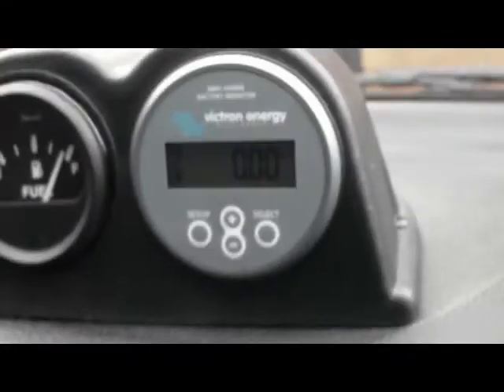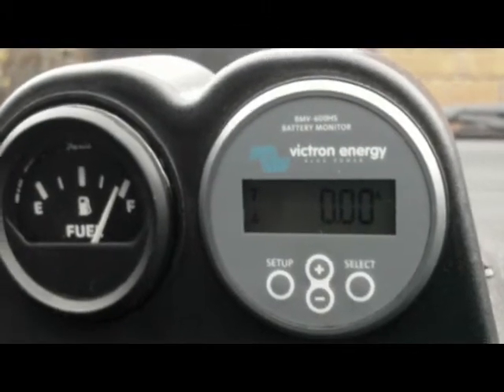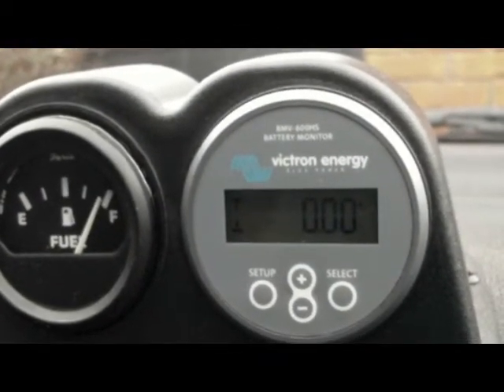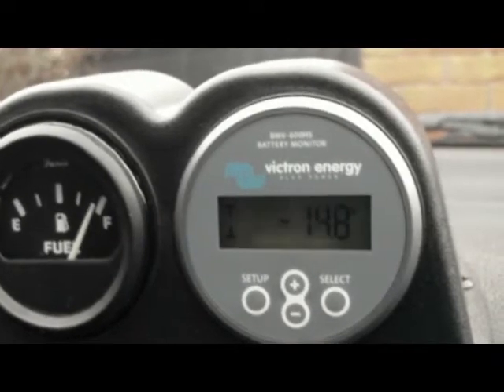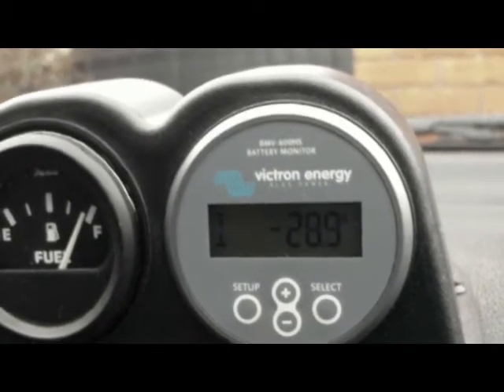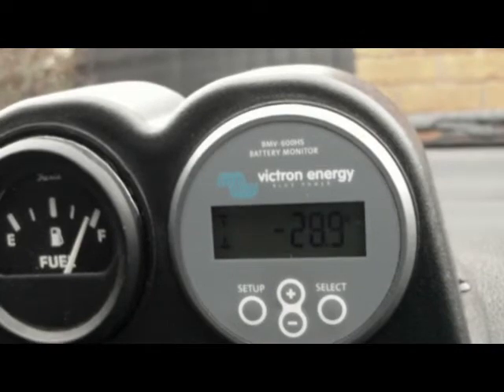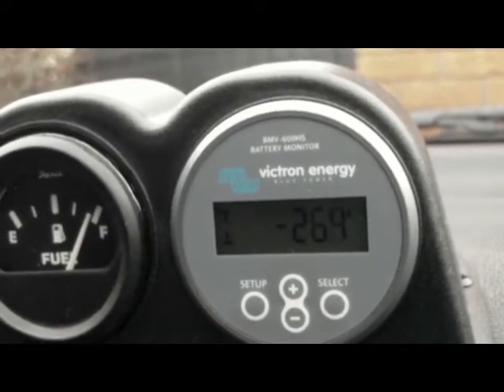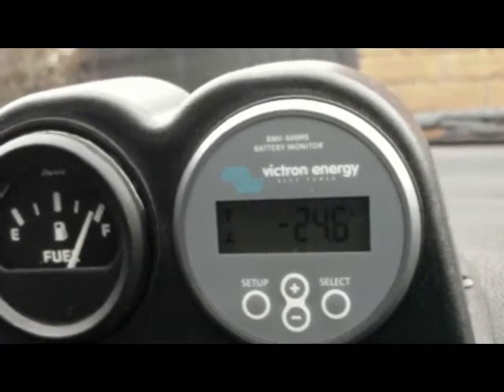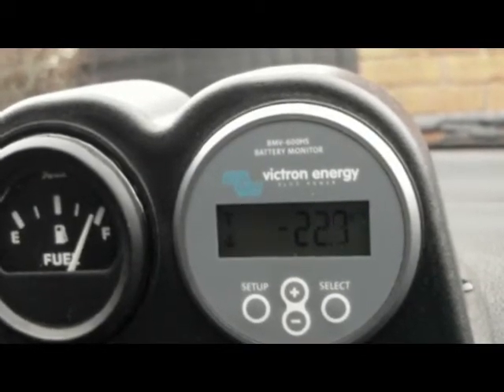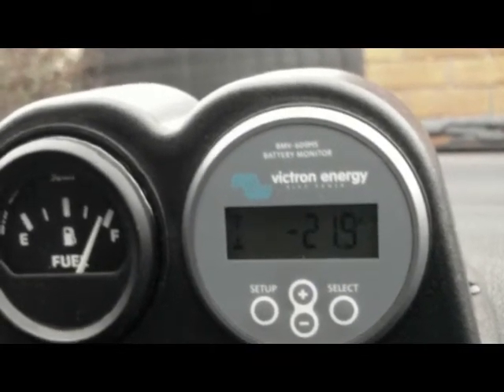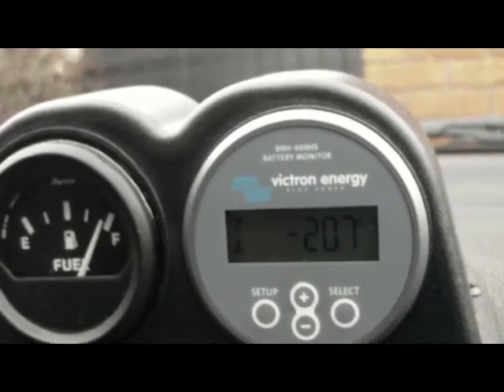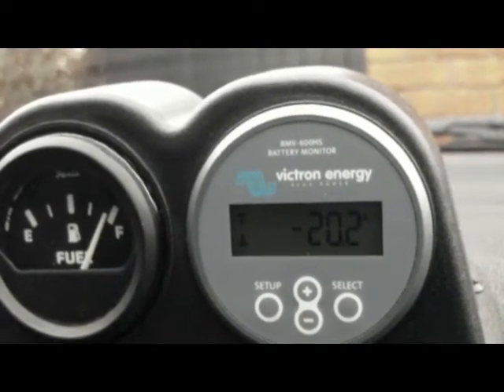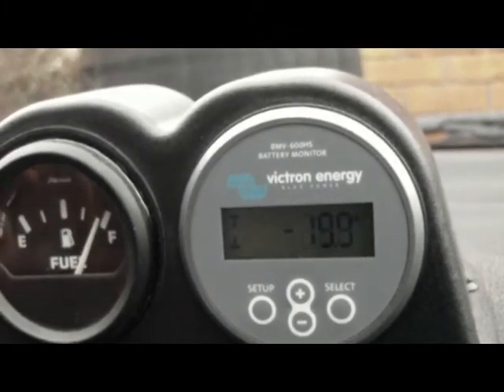So the fan is on, and I'm going to zoom in on the BMV so we'll see the current. I'm going to turn on the power to the actual core. There was a surge up to about 50 amps there. It's now just under 30, and it's starting to count back down. It'll settle around 20 amps. If we do the sums on that, 20 times 150 is about 3 kilowatts. And there's a lot of hot air coming out of here now.